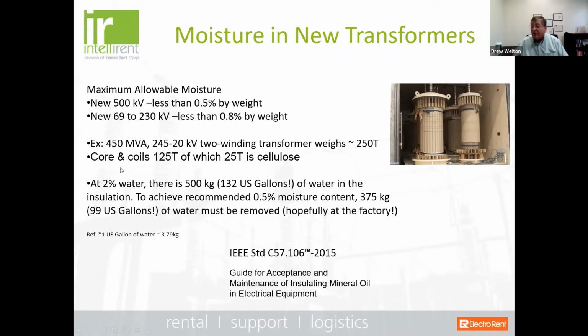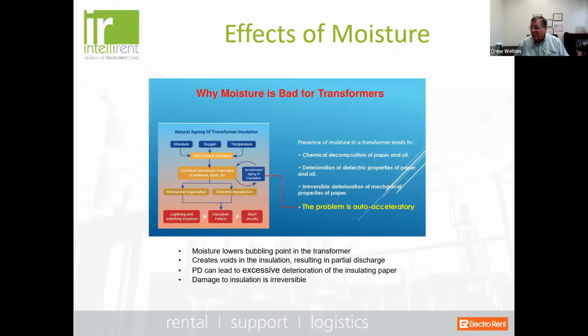So if we take an example, let's say we're looking at a fairly large transformer, 450 MVA, two-winding transformer, 245 to 20 kV, weighing about 250 tons. The core and the coils are about 125 tons, of which 25 tons is actually cellulose. At 2% water, there's 500 kilograms or 132 US gallons of water in the insulation itself. So to achieve the recommendation of getting down to 0.5% moisture content, we'd have to extract 99 gallons of water. So that gives you some correlation of what percentages of moisture content equate to in terms of the actual moisture itself.